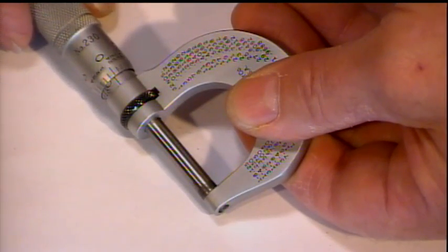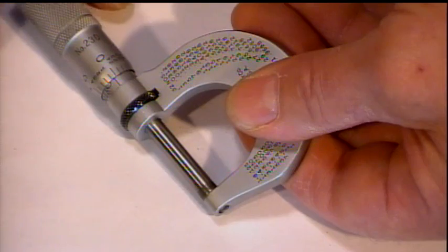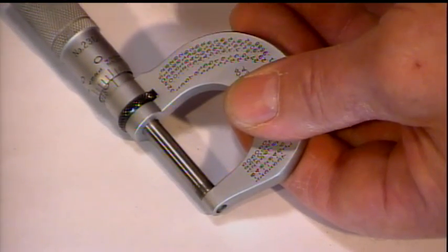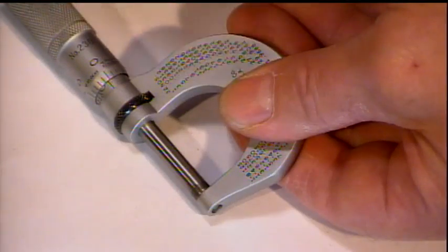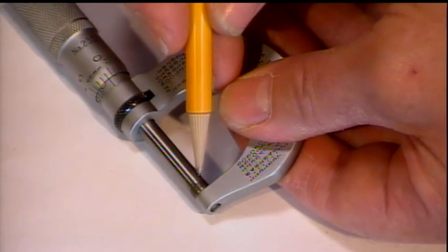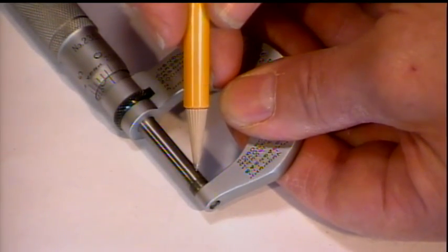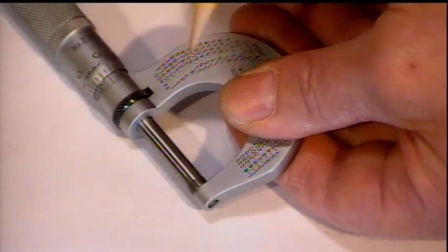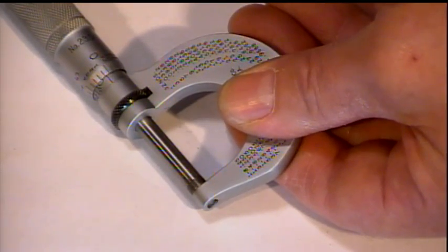If it does not line up on 0 when it's closed, there's a problem. And the first place we would look before doing anything would be for cleanliness or burrs. We'd be looking in here, hold it up to some light, run it on a piece of paper, see if it snags. Oh, so the reason it's not 0 is because there's a burr or something in there. It isn't closing all the way because there's something in there. Right.